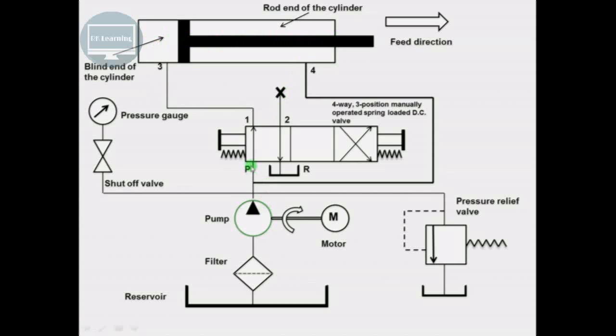Apart from the pump flow, the fluid from the rod end of the cylinder also gets added to the pump flow. Therefore, the volume of fluid supplied to the blind end of the cylinder is greater than the pump flow rate, and the speed of extension of the piston is greater than the retraction speed.